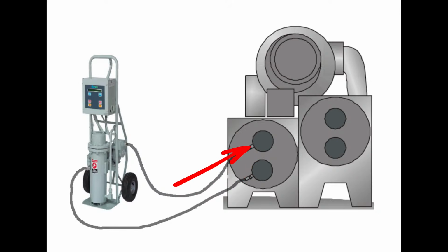Now, you absolutely will in some scenarios, but in many of them, especially if you're dealing with comfort cooling, it's not a process system with glycol, so you're not going to have any kind of treatment. It's something where only when the chemical guy comes out and checks the treatment levels on the evaporator or on the chilled water side are you going to see that. So that's why I'm cautious to do that approach, but it is a faster, better approach if capable, or if you're comfortable doing that.